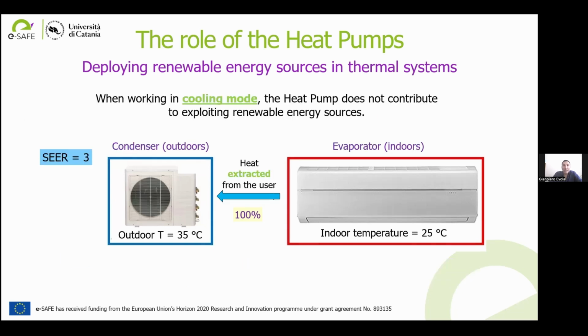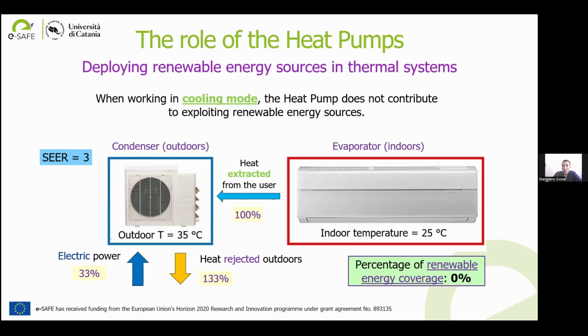Instead, when working in cooling mode in the summer, the same heat pump, which is reversible, of course, has a seasonal energy efficiency of, let's say, 3. So in this case, heat is extracted from the indoor environments. If the seasonal energy efficiency is 3, this means that 33% of the energy comes from electricity, and then all this thermal energy is rejected to the outdoors. Well, in this case, in this application, there is no use of renewable energy sources in the heat pump.